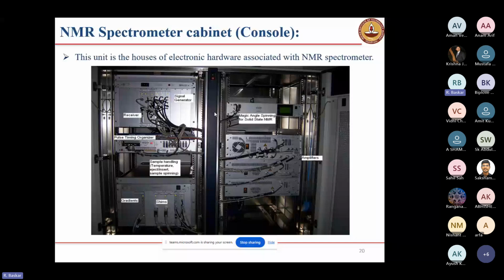Next, I'm moving on to the console. This is the console. These are the receivers, and here is the signal generator or synthesizer. Generally NMR people call it the synthesizer. This is the pulse timing organizer, which Bruker generally calls IPSO, intelligent pulse sequence organizer. And these are the shim boards, so gradients and all are here. In Bruker this is generally called BSMS. It helps to insert the sample, eject the sample, and spin the sample. Those are the things it checks. And this is for completely solid state.